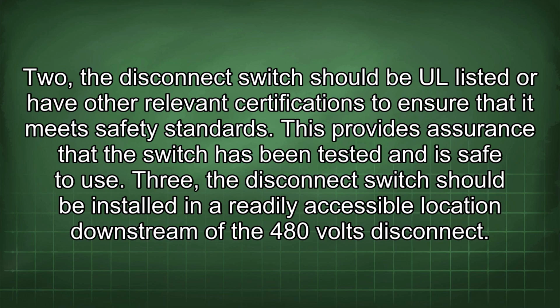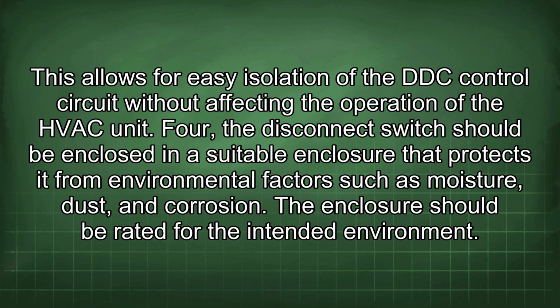2. The disconnect switch should be UL listed or have other relevant certifications to ensure that it meets safety standards. This provides assurance that the switch has been tested and is safe to use. 3. The disconnect switch should be installed in a readily accessible location downstream of the 480 volts disconnect. This allows for easy isolation of the DDC control circuit without affecting the operation of the HVAC unit. 4. The disconnect switch should be enclosed in a suitable enclosure that protects it from environmental factors such as moisture, dust, and corrosion. The enclosure should be rated for the intended environment.